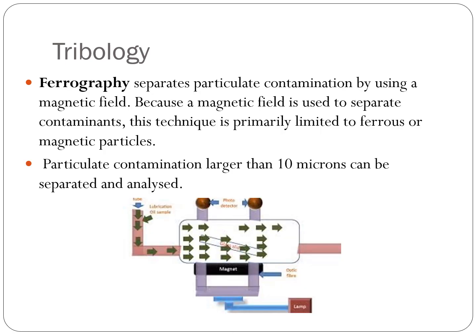Ferrography. Ferrography is another tribology technique. It separates particulate contamination by using a magnetic field. Because a magnetic field is used to separate contaminants, this technique is primarily limited to ferrous and magnetic particles. Particulate contamination larger than 10 microns can be separated and analyzed.